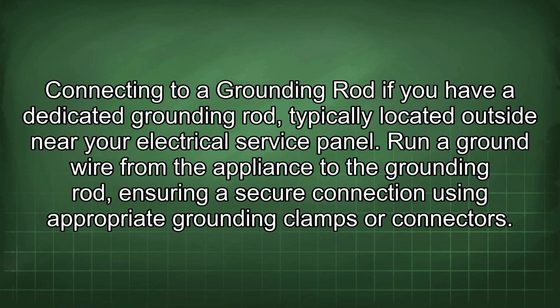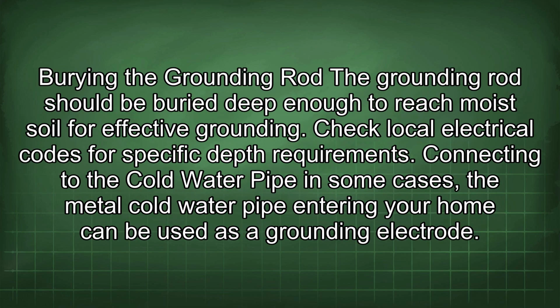Connecting to a grounding rod. If you have a dedicated grounding rod, typically located outside near your electrical service panel, run a ground wire from the appliance to the grounding rod, ensuring a secure connection using appropriate grounding clamps or connectors. The grounding rod should be buried deep enough to reach moist soil for effective grounding. Check local electrical codes for specific depth requirements.